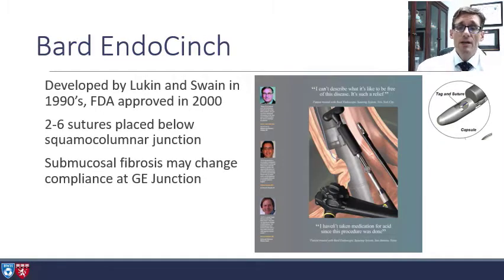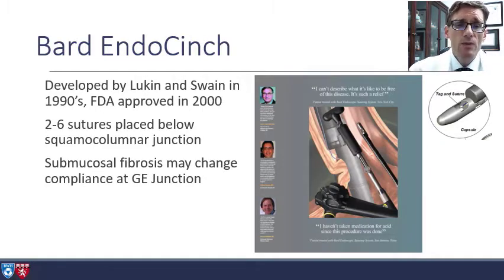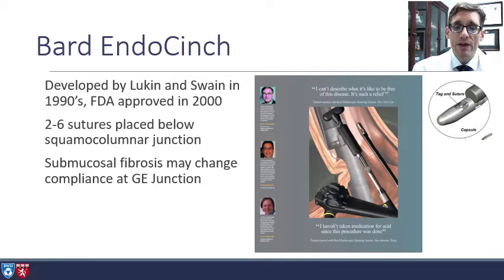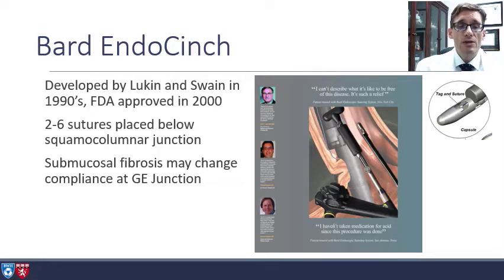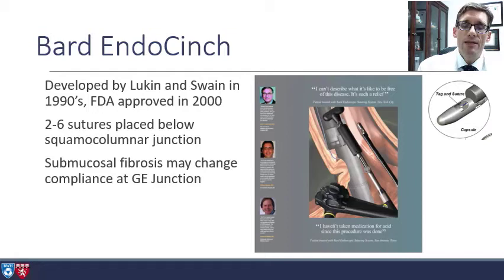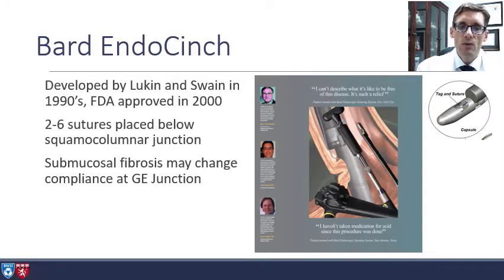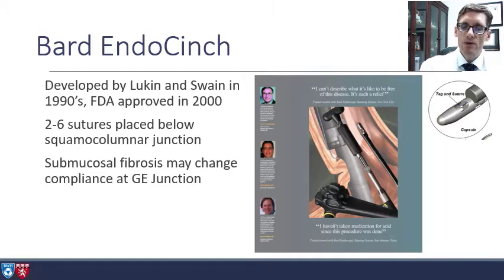The original device that focused on this was the Bard EndoCinch. This was FDA-approved in the United States in 2000. The goal was to place between 2 and 6 interrupted stitches at the gastroesophageal junction. It was a suction-based suturing device — tissue is aspirated into the device, a hollow needle is passed through the tissue and drops a T-tag, then the device is removed and the process repeated. The idea was that this would cause submucosal fibrosis and change the compliance of the gastroesophageal junction.